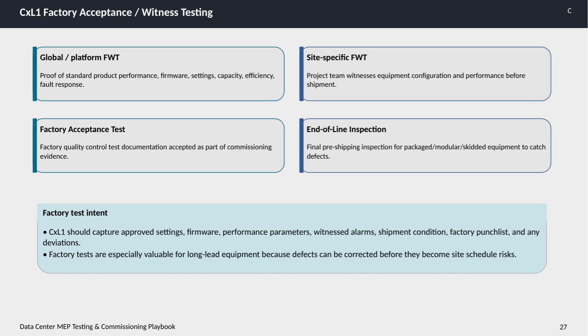The overall intent of factory testing is to thoroughly document approved settings, firmware versions, performance parameters, any alarms witnessed, shipment conditions, punch lists, and deviations. This documentation is especially valuable for long lead equipment because identifying and fixing defects early prevents delays on site, protecting the project schedule.